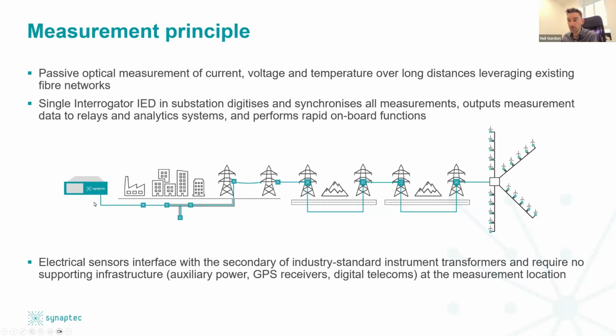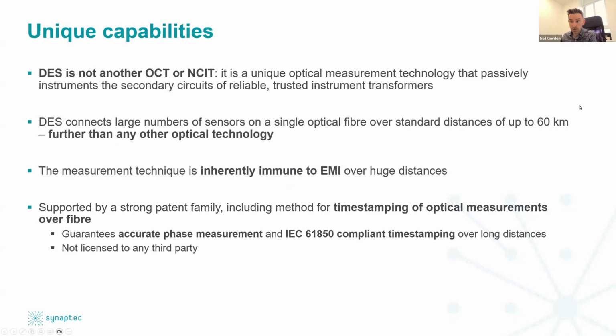So we have all those sensors installed throughout the network, and then at a central location, usually in a substation, we have our interrogators. What those do is receive the measurement data from all the sensors in that fiber array, digitize it, locally synchronize all those measurements, and output measurement data. They perform analytic functions for long-term trends and condition monitoring, and they perform rapid onboard functions to enable things like protection applications or protection enhancement applications. So that's broadly what this scheme looks like, but what's really unique about it?